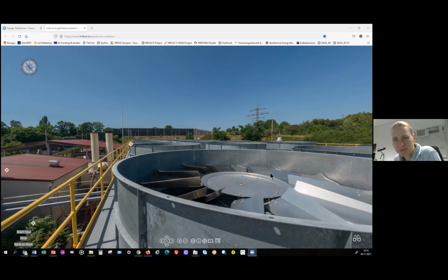Another question on seismicity: what is the approach on flow rates and pressures used to keep induced seismic events below felt levels for the local population? We can assure this by ramping down and ramping up the flow rate before an intended shutdown of the unit. For example, for a planned maintenance shutdown, as we do for preventive maintenance in our power plant, we reduce the flow rate over a period of around 2 or 3 weeks. And when restarting after a longer shutdown, as we unfortunately had due to the mentioned pump issue in the summer, the restarting period takes about 6 weeks. This way, we are able to keep the induced seismicity very well controlled.